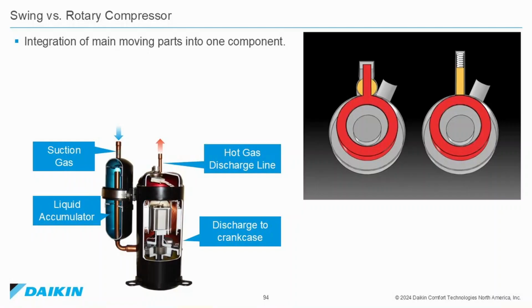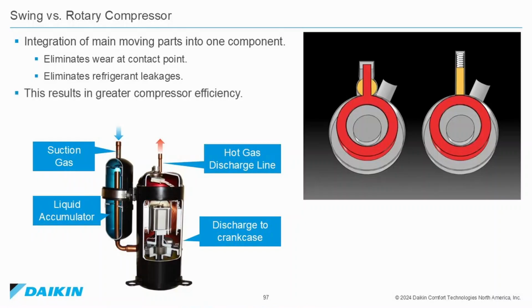A swing compressor versus a rotary compressor. Integration of main moving parts into one component eliminates wear at the contact point and eliminates refrigerant leakage. The result is greater compressor efficiency.